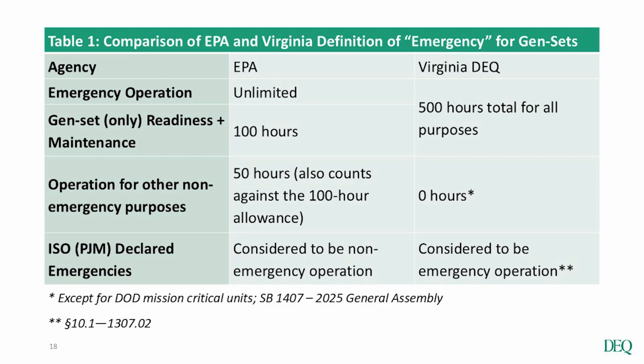So I just talked a little bit about emergency. This is something that we put in our data center permits for the gensets that are designated as emergency units. There are a certain set of operating requirements. So when you apply to us for an emergency unit, under the old paradigm, you did not have to put on as stringent controls. The trade-off for that was we would restrict those data center genset operations to much more prescribed periods of time. So true emergencies, the maintenance and readiness testing that we described, and then something that the General Assembly put in place some time ago, which was operation for an independent system operator declared emergency. In Virginia, that is PJM. When they declare an emergency, the General Assembly passed legislation specifying that operation during those events would count as emergency towards Virginia's definition.